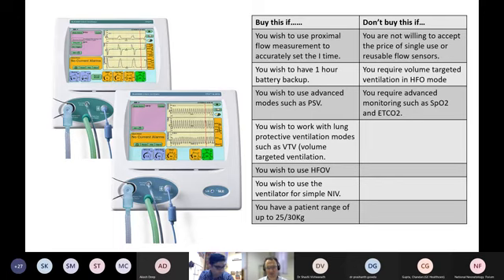This step up in flow sensor technology also brings in new modalities. So the mode pressure support ventilation, which is commonly found on many, if not nearly all, infant ventilators now, as well as adult ventilators, requires the flow sensor to be able to allow the infant to determine how frequently it wishes to breathe, and also how deeply the baby breathes. So the flow sensor determines the length of the breath, or helps to determine the length of the breath that the baby takes in pressure support ventilation. So this is a new modality that you would see in a ventilator such as the 4000 and the 5000.